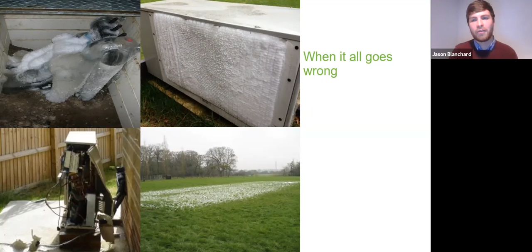And what happens when it goes wrong? Well, we've looked at this one in the bottom right here. What happens if you incorrectly size, under design, or undersize a ground source horizontal loop? Actually, you can also freeze manifolds with this problem. Air source heat pumps, if undersized or incorrectly installed, can become quite expensive blocks of ice for you. And indeed, in extreme situations, the compressors can effectively break completely. This was quite a catastrophic failure due to an air source being significantly undersized, and I mean half the size it should have been.